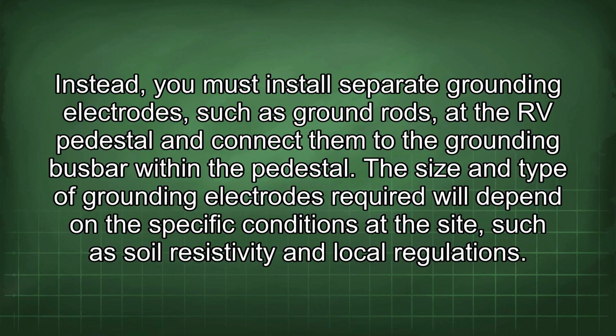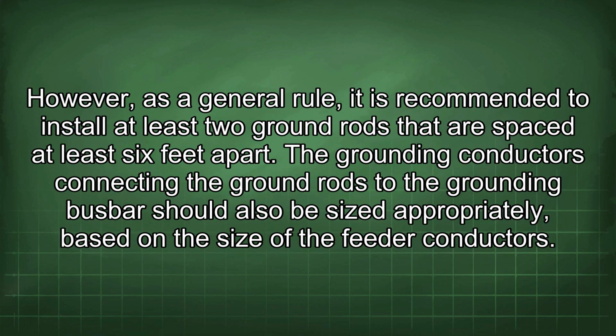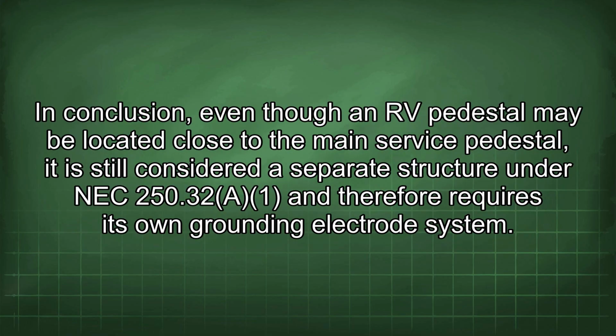The size and type of grounding electrodes required will depend on the specific conditions at the site, such as soil resistivity and local regulations. However, as a general rule, it is recommended to install at least 2 ground rods that are spaced at least 6 feet apart. The grounding conductors connecting the ground rods to the grounding busbar should also be sized appropriately, based on the size of the feeder conductors.